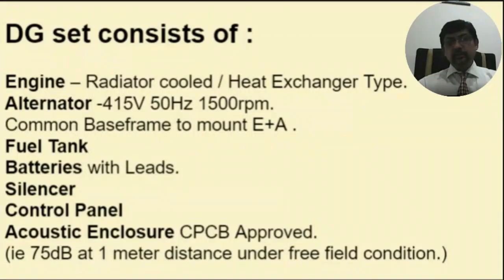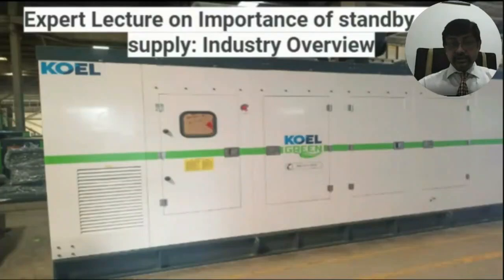Basically, ammeter, voltmeter, frequency meter, kWh meter, and kW, that is kilowatt. These are the five parameters, and for the largest generator, the sixth is power factor. Then coming to the next and the last, which is most important, the acoustic generator. Yes, this is the acoustic. This is a Kirloskar generator, and this is an acoustic enclosure inside which the generator is housed.